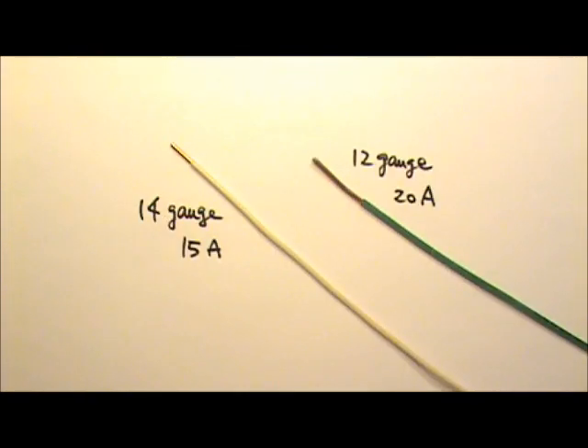Wires are rated by the maximum current they can handle safely. For example, this 14 gauge wire is rated for 15 amps of current. This thicker 12 gauge wire is rated for 20 amps.